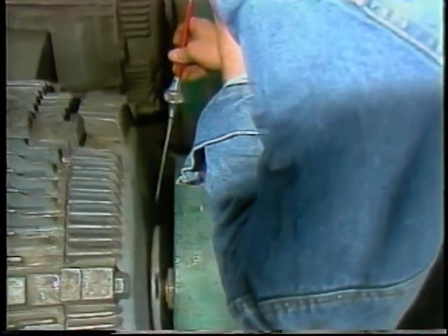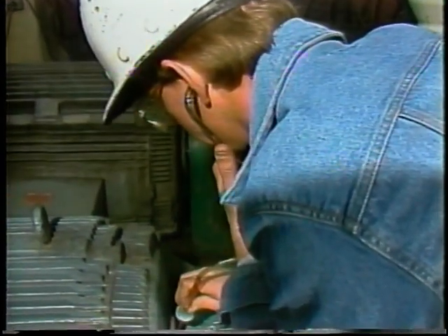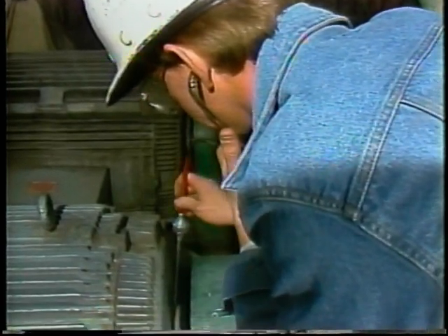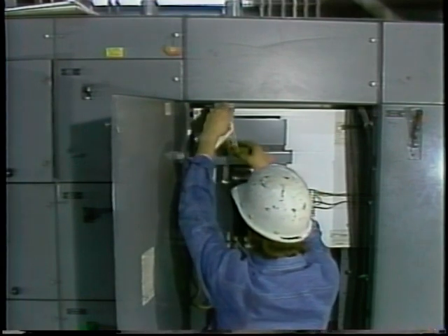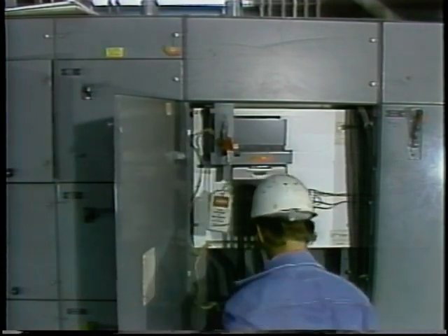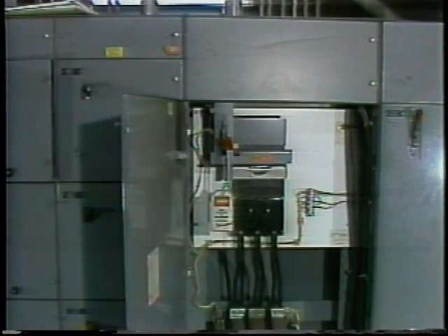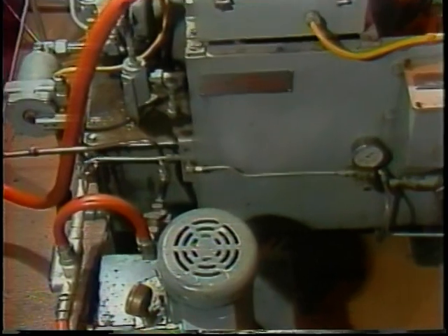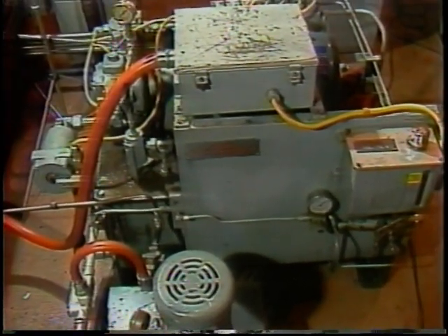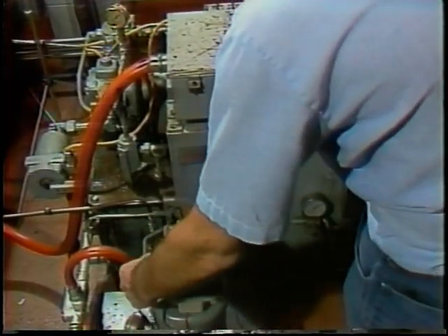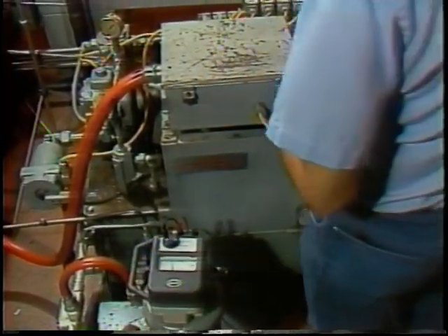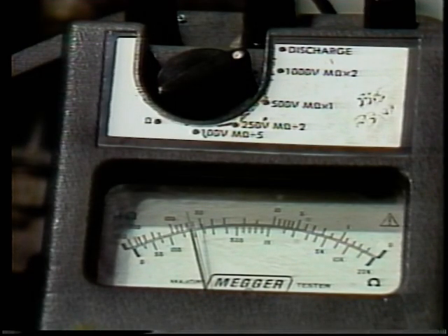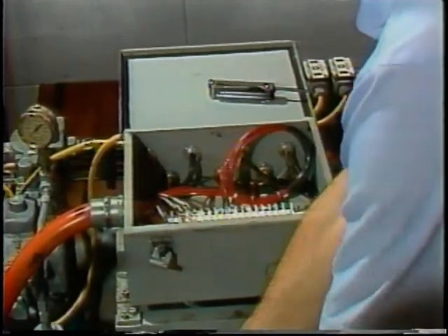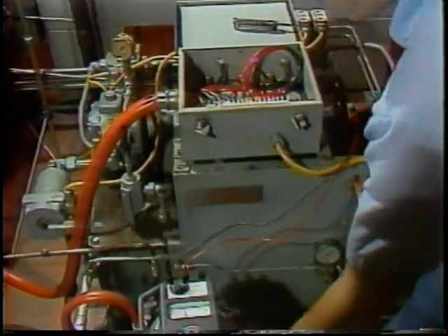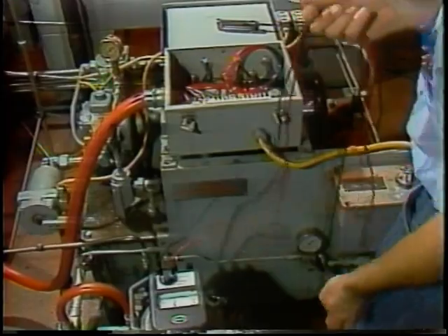Vibration, squealing, or dragging or scraping noises in any motor probably means serious bearing problems or a rubbing rotor. Other motor problems may not be so obvious, however. To find them before they damage the motor takes instruments and careful record keeping. In many plants, for example, the insulation inside a motor is periodically checked with a megohmmeter. Unlike a standard ohmmeter, which uses a small battery to push current through the test resistance, a megohmmeter uses a high voltage equal to or greater than normal power line voltage. This allows it to measure very high resistances accurately. It also puts the insulation under high voltage stress, so defects are more likely to show up.